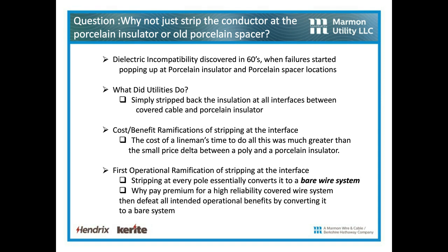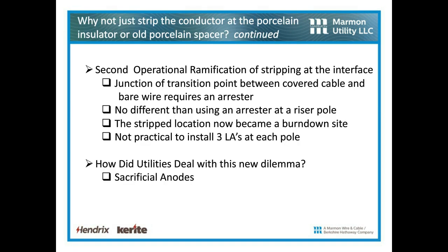The first operational ramification of stripping at that interface is that stripping at every pole essentially converts it to a bare wire system. Why pay a premium for a high reliability covered wire system and defeat all intended benefits by converting it to a bare wire system at every pole? It just didn't make sense. The second operational ramification is that now I created a junction or transition point between covered conductor and bare wire. Any transition is going to require an arrestor, the same as I'm using an arrestor at a riser pole, the transition between bare wire and underground cable. So the stripped location now becomes a burn down site, and it's not practical to install 3 lightning arrestors at each pole. So how did utilities deal with that?